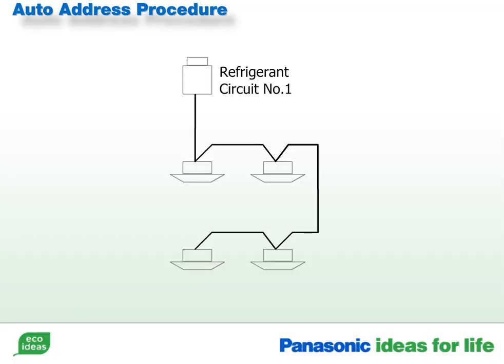Let's take a closer look at the auto address procedure and how the settings are applied to the refrigerant circuit. In this example, we have one refrigerant circuit. When refrigerant circuit number 1 has completed addressing, the condenser will assign the indoor unit number. Refrigerant circuit number 1 has been fully addressed. The first digit represents the refrigerant circuit number. This value was set when the refrigerant circuit number was configured on the main board on the main outdoor unit. The second digit is applied by the condenser board during the auto address procedure. The indoor unit number is randomly applied by the main board in the outdoor unit.